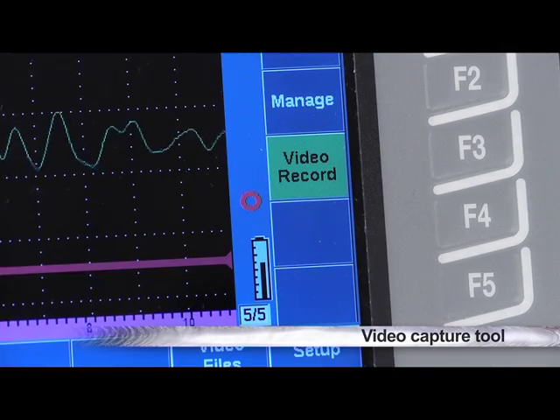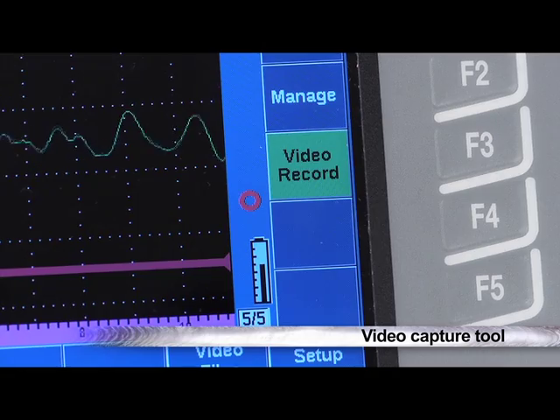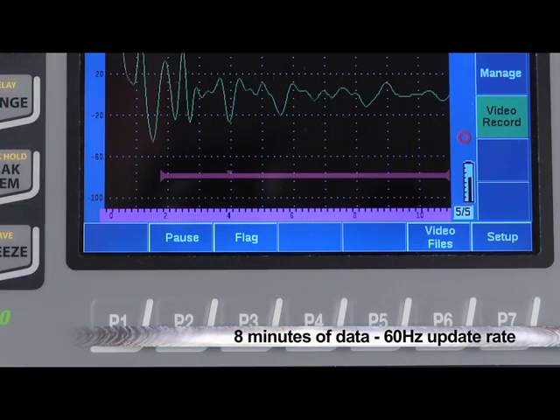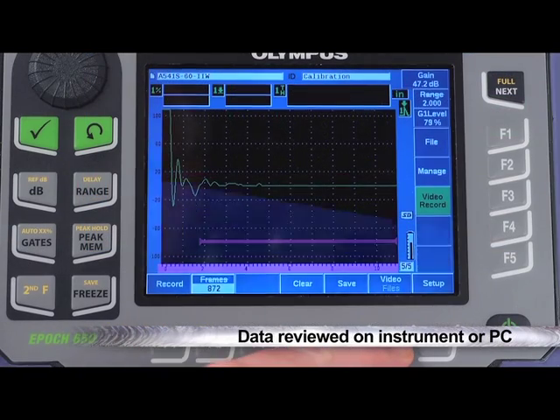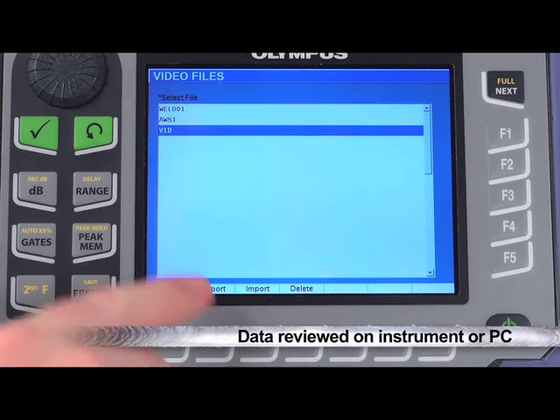To enhance static reporting capabilities, the EPOCH 650 comes standard with a video capture tool. This video record function collects up to 8 minutes of data at a full-screen update rate of 60Hz. The data can be reviewed onboard the EPOCH or quickly transferred to a PC for review and archiving.